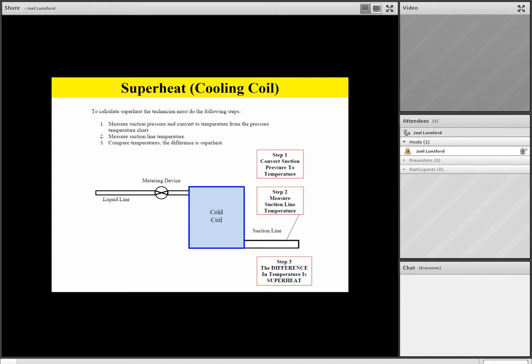In the heating mode of operation, because we're building a lot of ice on the outdoor coil, superheat can vary somewhat on a heat pump. So normal superheat in the cooling mode of operation is 10 to 15, we learned a minute ago. But in the heating mode of operation, normal superheat can range anywhere from about 4 degrees to 15 degrees. So again, we have to swing our superheat value around a little bit in the heating mode, because as we start building ice on the coil outside, that's going to drive the superheat low on that cold coil. So in the heating mode, about 4 to 15 degrees will be considered normal on a heat pump, and about 10 to 15 degrees in the cooling mode will be a good normal parameter.